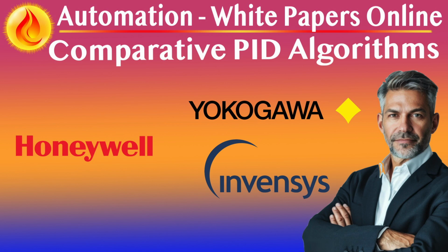Invensys Foxboro offers tools like Loop View, Control Expert, and integration with Connoisseur for advanced process control diagnostics. These tools allow plant-wide loop assessment, model-based tuning, and constraint visualization. However, they may require more specialized knowledge to use effectively. For hybrid teams, operators and engineers, Honeywell offers more immediate usability. For centralized control teams or plants with high process engineering sophistication, Foxborough's toolset offers deeper diagnostics and advanced tuning capabilities.